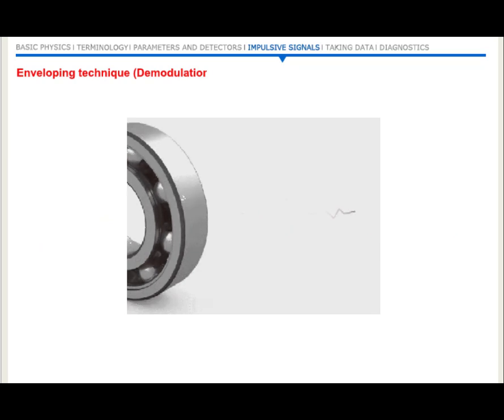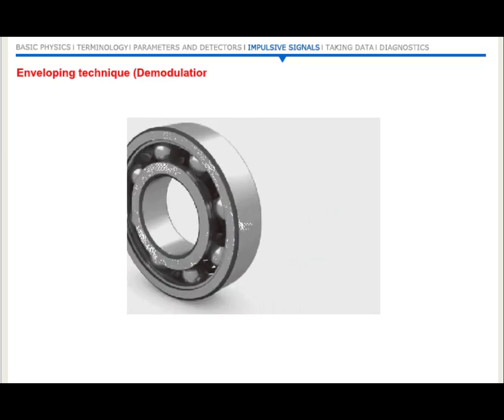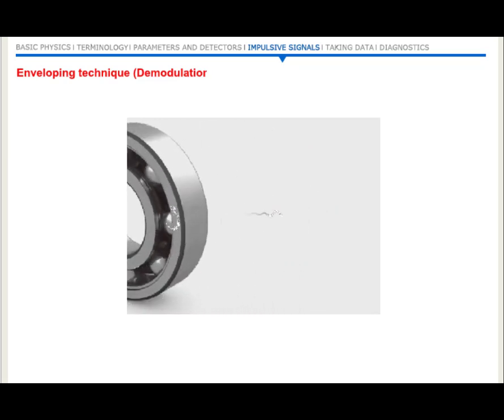To detect bearing damage in its early stages, a technique is needed that can detect the small impulsive signals that are generated when impacts occur between microscopic flaws in bearing elements. This vibration is typically very small in comparison with general machinery vibration resulting from misalignment or unbalance. So it becomes evident that simply monitoring the RMS vibration level is inadequate for this task. Whilst this is effective for detection of common machinery faults such as unbalance, misalignment and looseness, it cannot be relied on to give early warning of impending bearing problems.